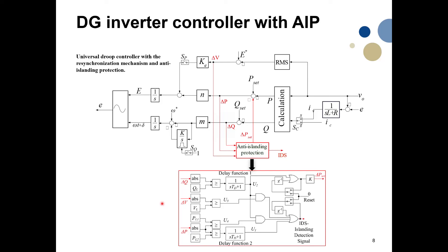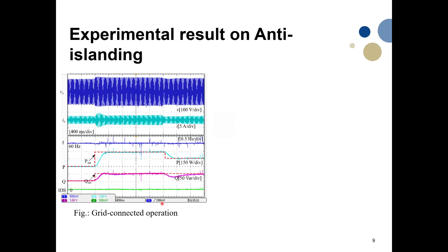We tested this anti-islanding detection for different scenarios. In the first scenario, we performed offline synchronization, turned on the converter, and it supplied power to the grid. The green line is the islanding detection signal. We changed the power reference of the inverter and it follows the reference accordingly for both active and reactive power. The system is stable, and during the power reference change, the islanding detection signal remains zero — meaning no false islanding detection is triggered.